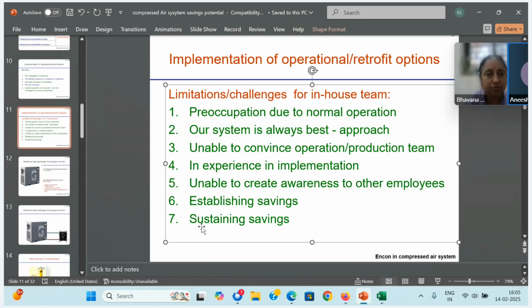So here actually the first question I asked was regarding the BLDC screw compressor. Nowadays a lot of people are using old screw compressors, so we are finding some technology to upgrade to a better specific power consumption. Mostly the best figure I have measured for a screw compressor is 0.17 kilowatt per CFM. Just like you wanted for compressor, I wanted for chiller. Yes, for screw compressor, the best figure we have found in the audits completed till today is 0.17.